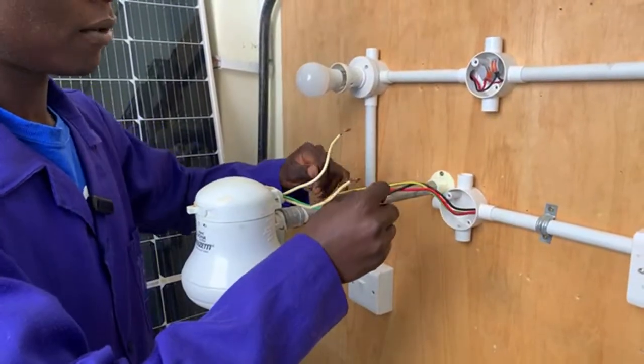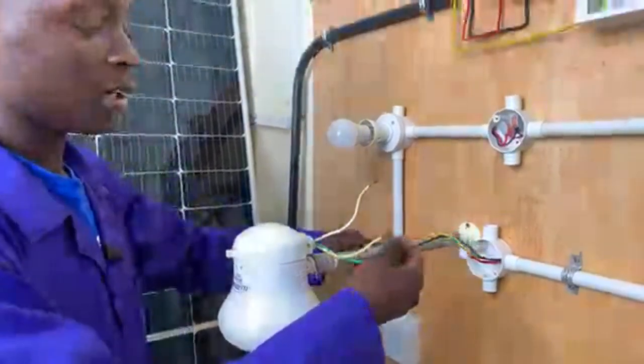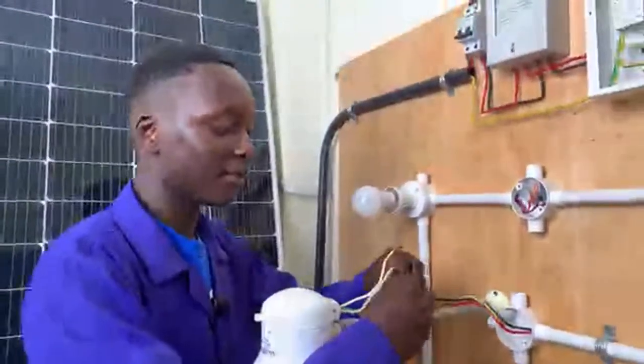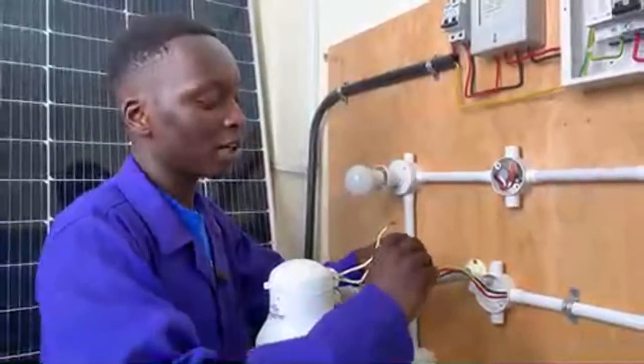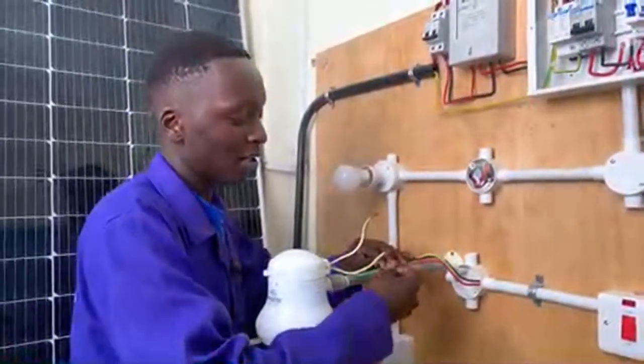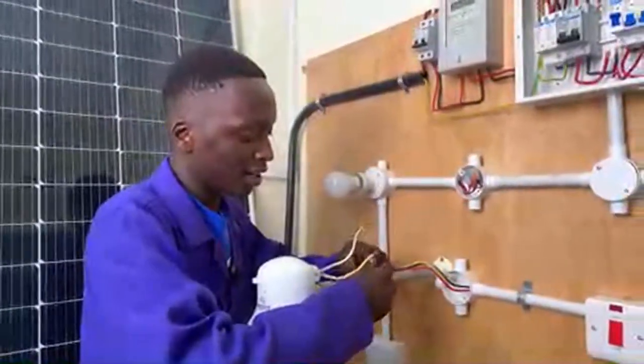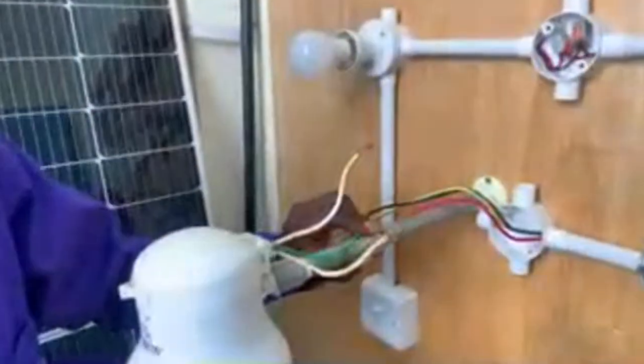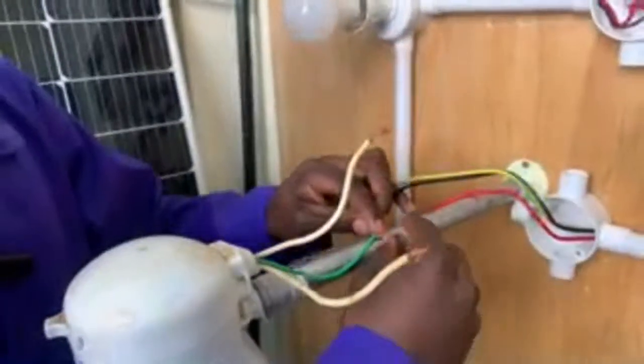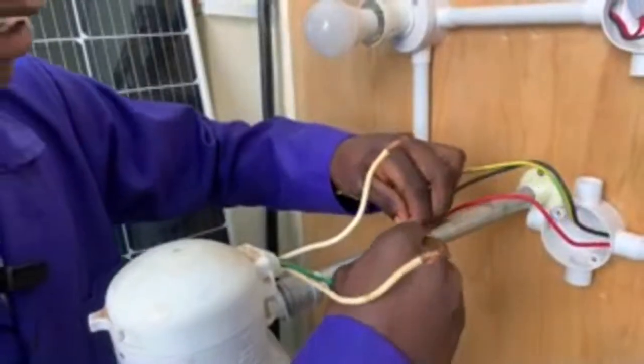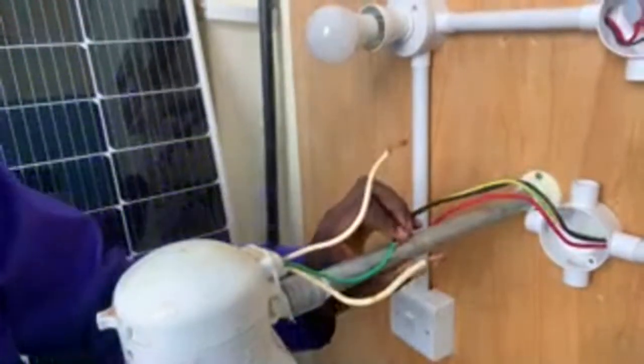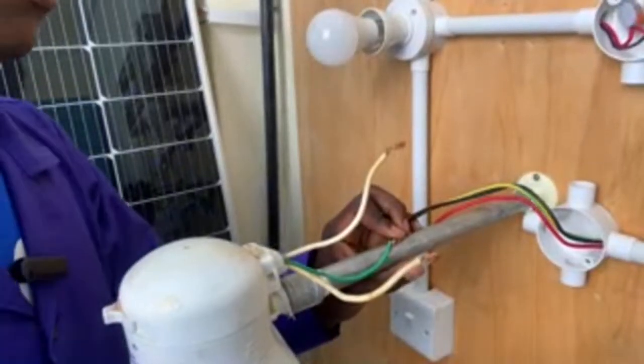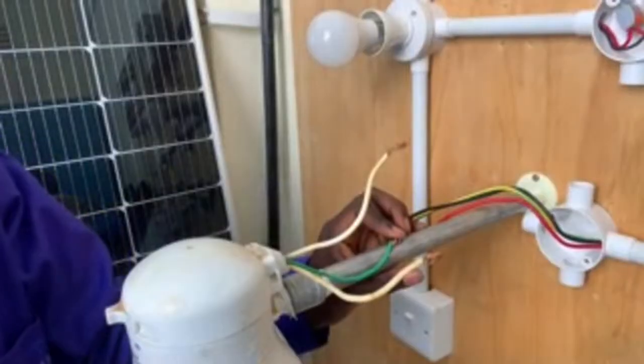The other thing I found out with our electricians is that when doing earthing, after connecting their joints, they come and put their wires at this pipe like this. That is the earth connection, at this metallic pipe. I think they are trying to do the earthing with the metallic pipe, and this may cause a fault. In case that house has an earthing fault, this can cause electrical shock even at the taps, as someone is turning the water on. Correct, I agree with you.